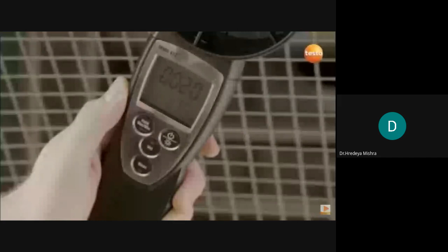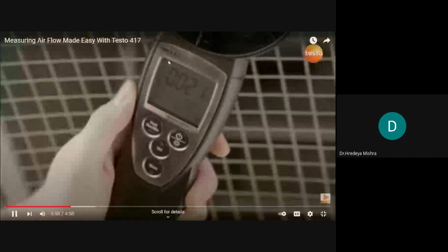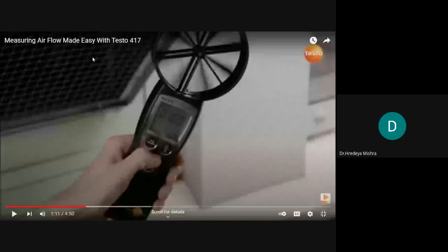When measuring at the supply air outlets, take into account that different flow rates occur at the outlet area because of the air outlet grill. This is why the vane is moved across the ventilation grill to measure the outlet airflow. The Testo 417 automatically generates an average value. In the process, make sure not to block the air outlet unnecessarily, because any flow resistance affects the measurement result.